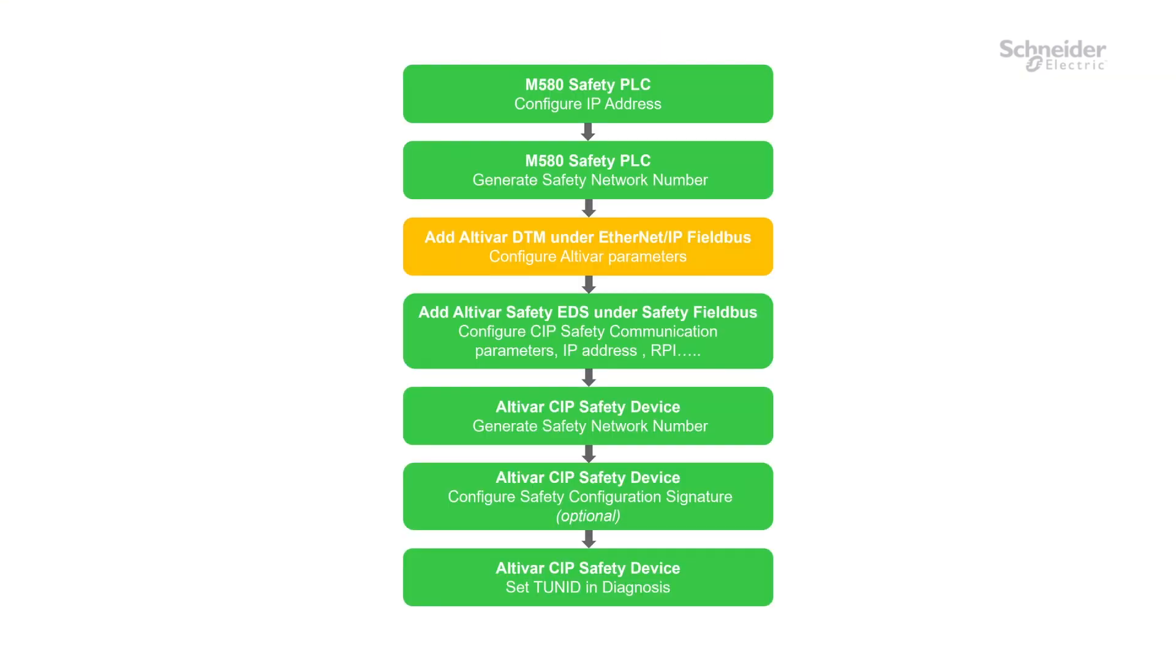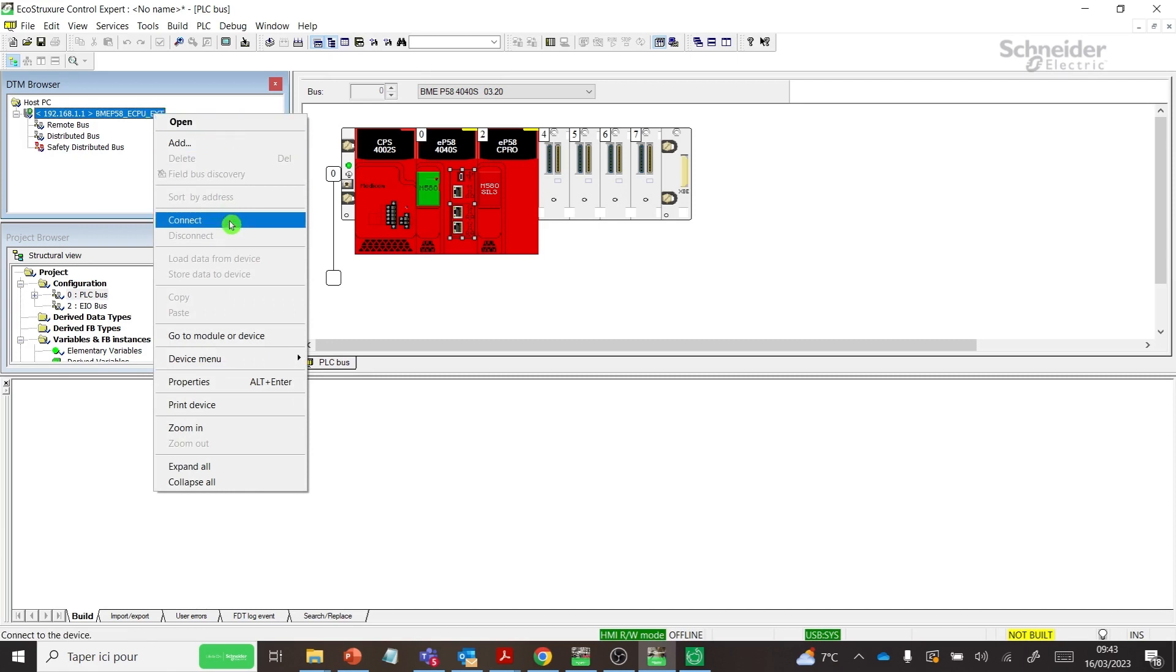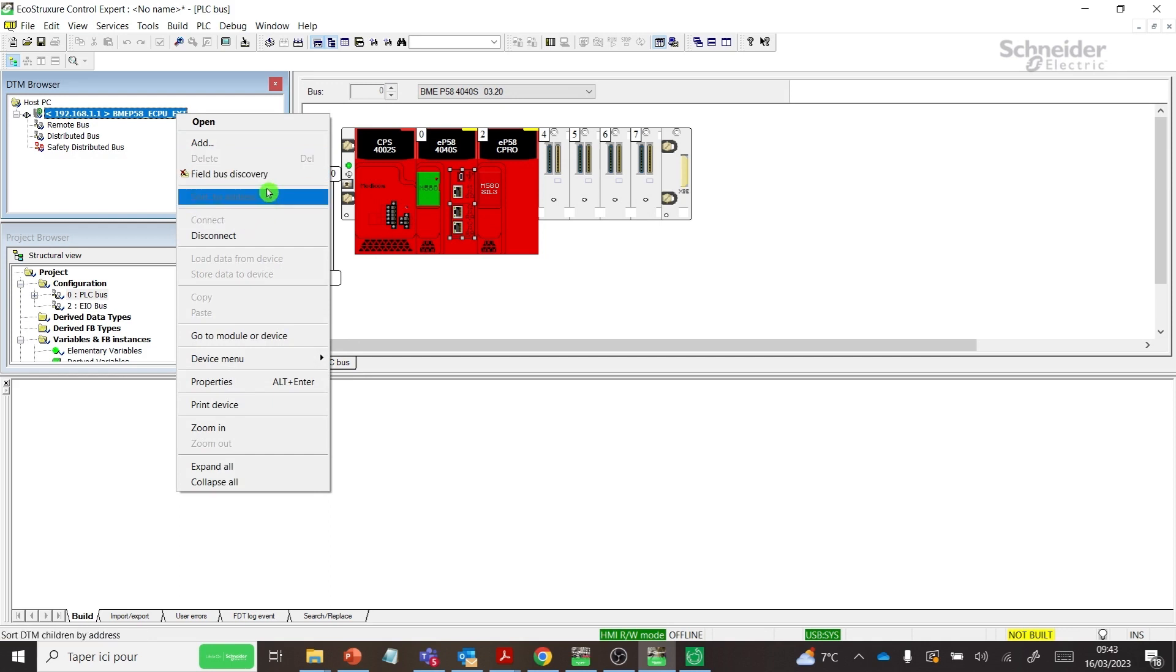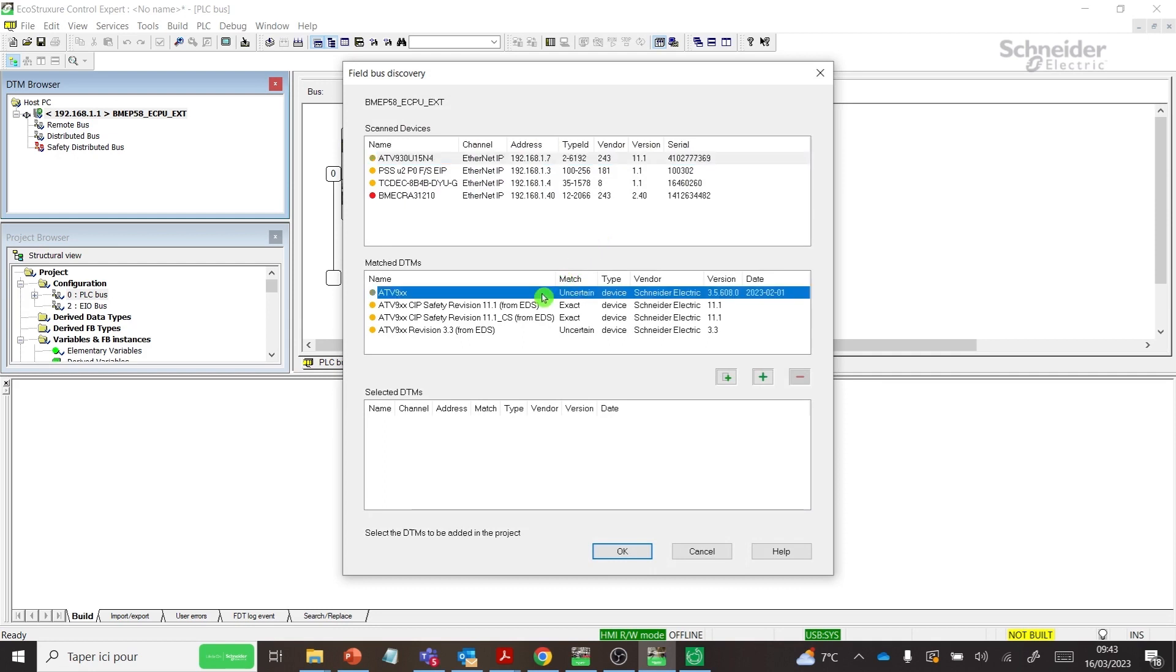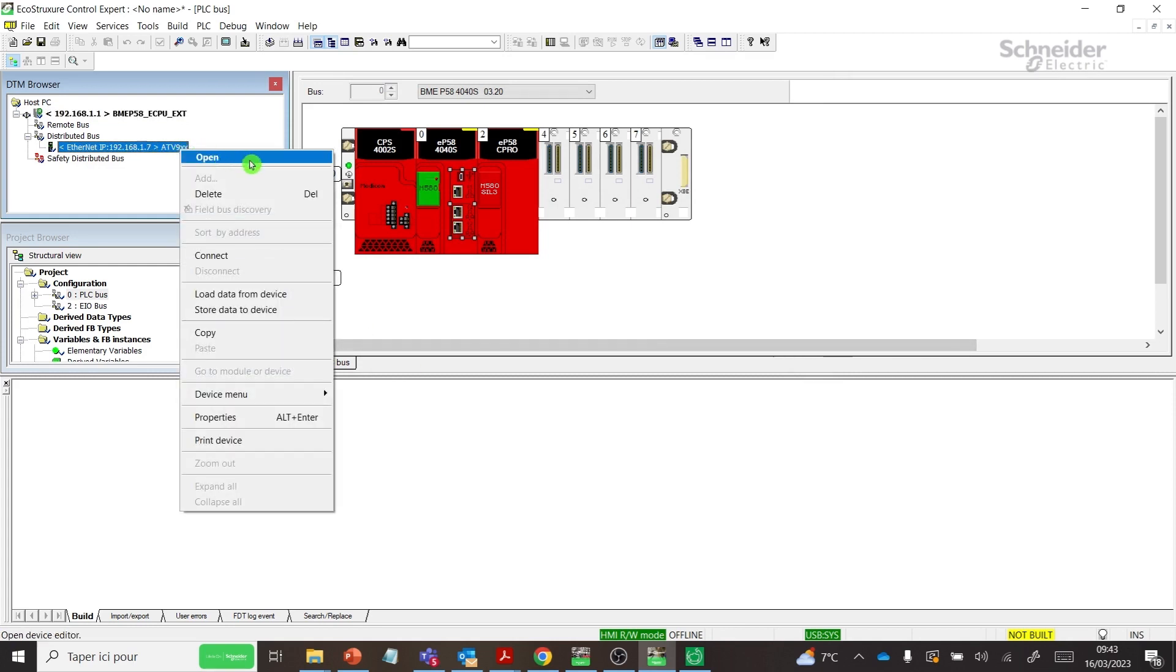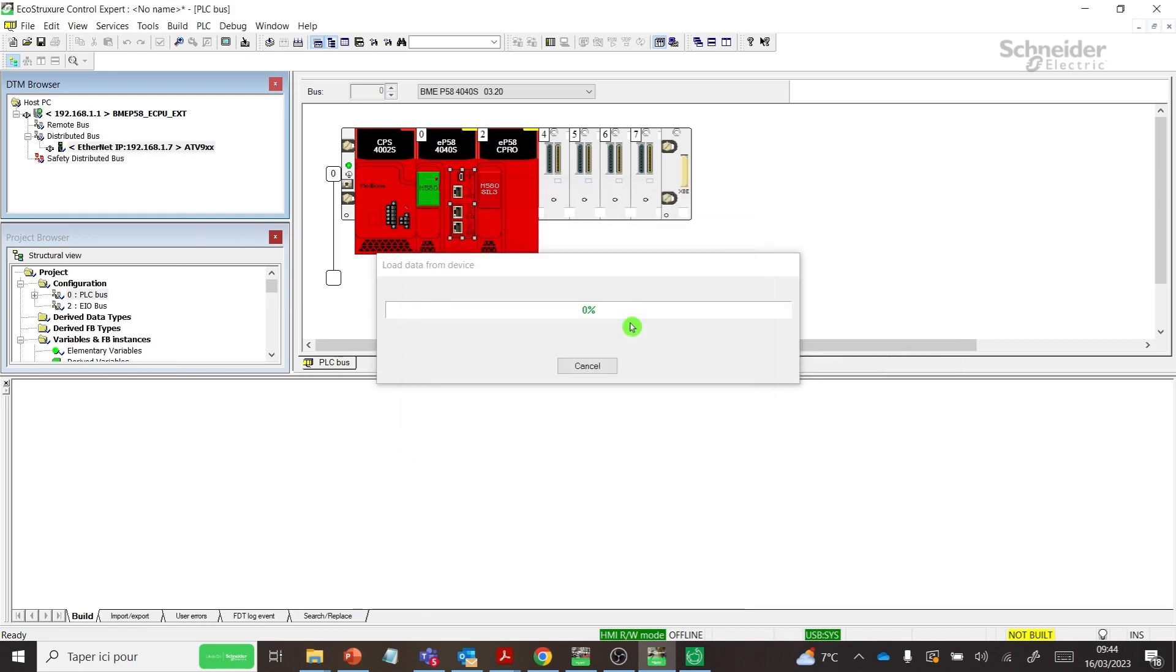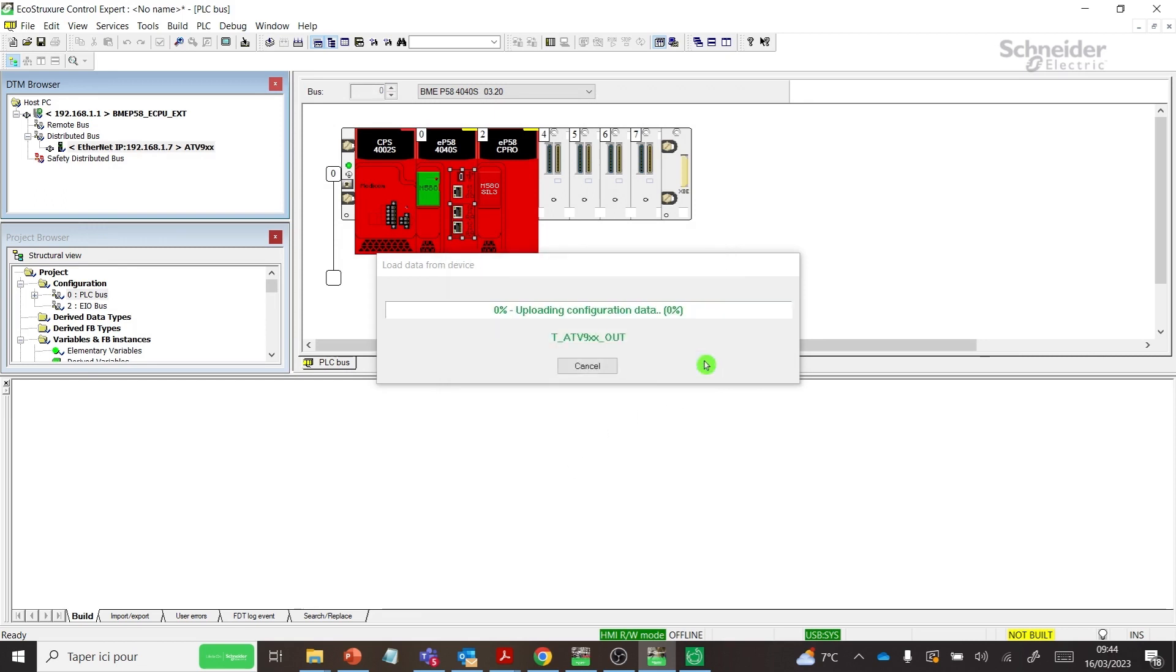Step 3: Add Altivar DTM under Ethernet IP Fieldbus. Open the FDT DTM Browser. Right-click Master PLC DTM and connect. Then do a Fieldbus Discovery using Ethernet IP Channel. First, select your CIP Safety Drive, then select the Match DTMs. Click on the Plus button and Confirm. Select Load Data from Device. Enter the User Name Admin and Default Password will be Web Server Password. You can find it with the Graphic Display Terminal in My Preferences MYP menu, then Web Server WBS.